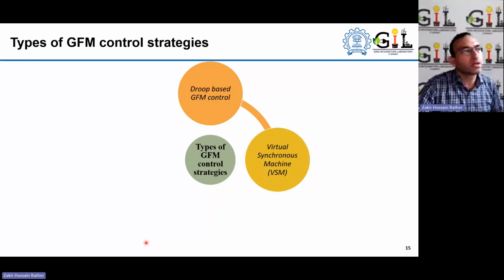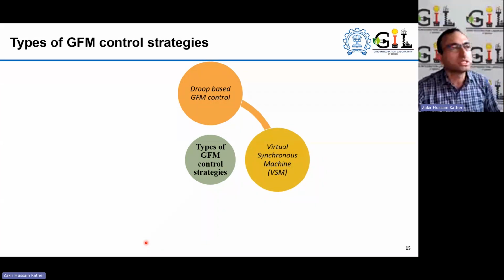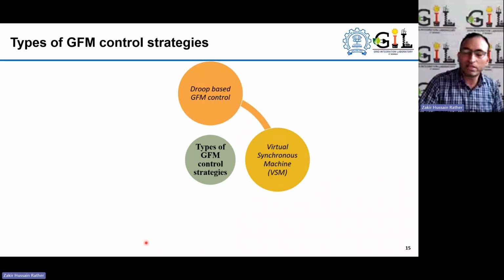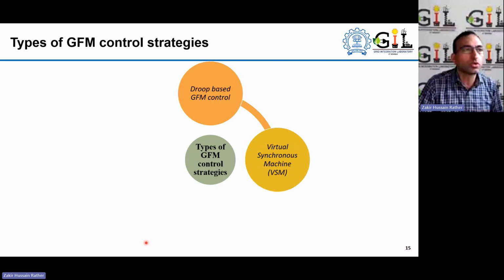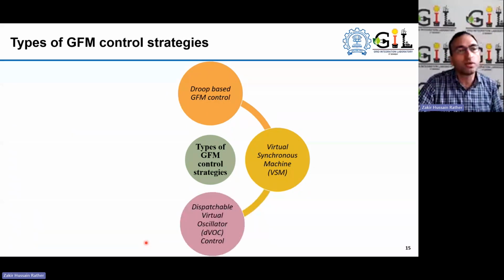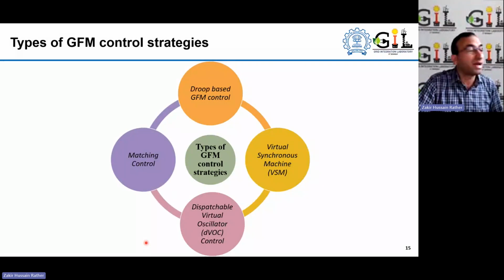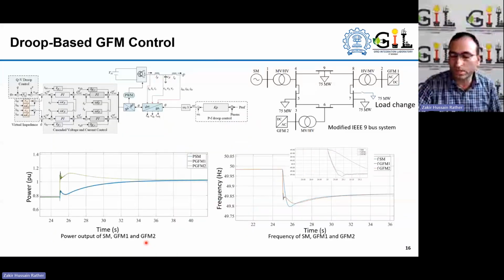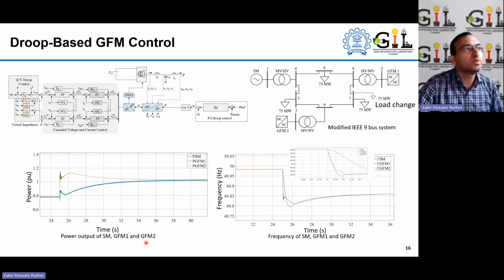In terms of the control philosophy or control schemes, we can divide it broadly into droop-based grid forming control, virtual synchronous machine control, virtual oscillator control, and matching control, and there are several subcategories, which in the interest of time we will not go into. But you can say broadly, these are some of the major categories of control for this grid forming technology. For example, this is droop-based grid forming technology here at IIT Bombay.